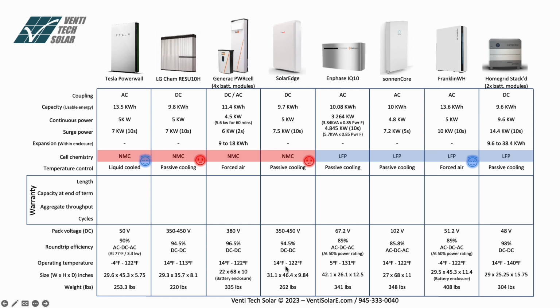And then here in the SolarEdge, they're saying they're matching Generac, 14 degrees Fahrenheit to 122 degrees. For passive cooling, this is a stretch. NMC batteries should not be operating at 122 degrees. This is definitely, I would think, a stretch of the technology.